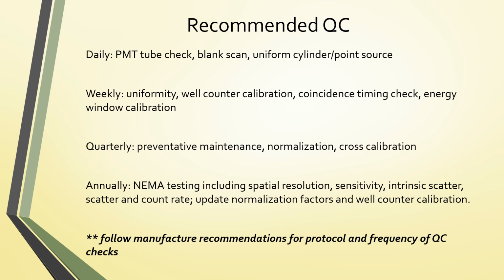Some of those may be done monthly if your scanner is stable, hasn't had any issues, and more frequently if you're in a high volume place. Quarterly preventative maintenance, normalization, and cross calibration, and then annually that NEMA testing may need repeated, including spatial resolution, sensitivity, intrinsic scatter, scatter and count rate, updated normalization factors, and the well counter calibration.